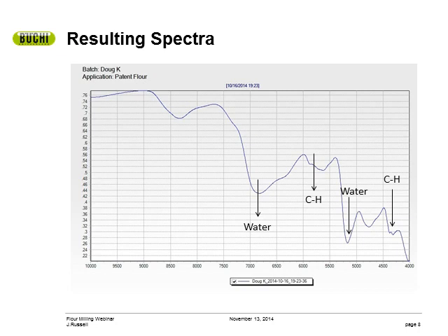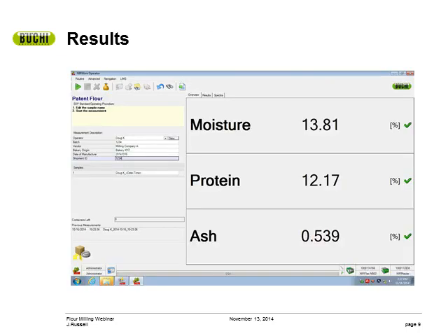Understanding a little bit about the science does take away the mystery and helps you build confidence in your NIR. This is what the result page looks like on the BUCHI NIRMaster. Next to each result is a green checkmark indicating two things: number one, the sample is spectrally similar to the calibration sample pool, and number two, the results are within the concentration range used to make the calibration. This green checkmark verifies the spectrometer has seen a sample similar to this one and has correctly interpreted the spectra.